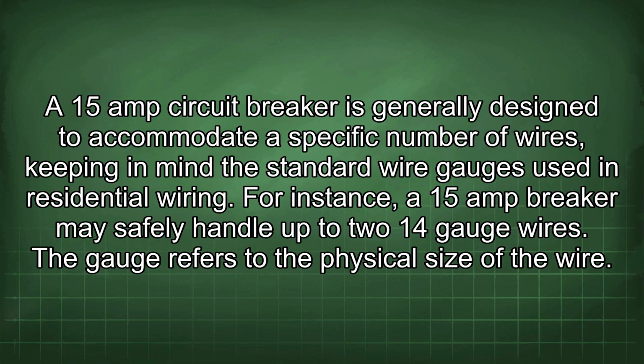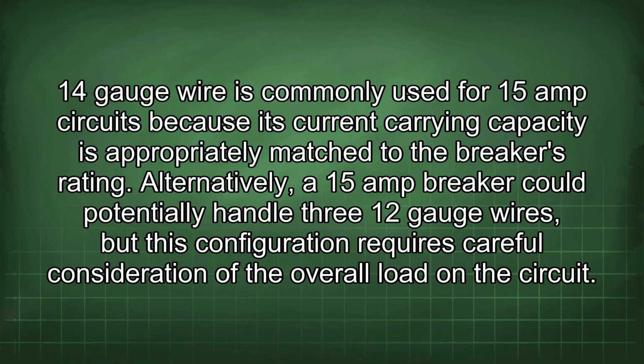A 15-amp circuit breaker is generally designed to accommodate a specific number of wires, keeping in mind the standard wire gauges used in residential wiring. For instance, a 15-amp breaker may safely handle up to two 14-gauge wires. The gauge refers to the physical size of the wire. 14-gauge wire is commonly used for 15-amp circuits because its current carrying capacity is appropriately matched to the breaker's rating.